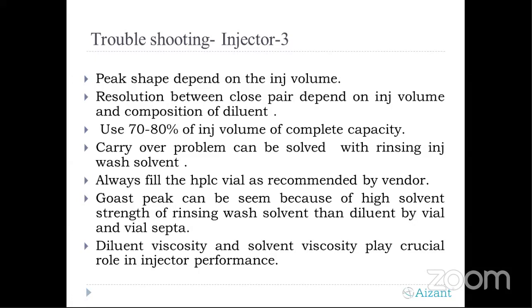Coming to the third slide on the injector, the peak shape of your chromatography is dependent upon injection volume. During development, you can easily cross-check that with variations of 10 microliter, 20 microliter, 50 microliter, and see how the peak shapes come out. It will also depend on the previous point we highlighted, the diluent polarity with respect to the mobile phase. Even if the polarity is different, with 10 microliter you won't face those challenges. But as you enhance your injection volume and the mobile phase remains the same, you will get distortion in the peak shape. So injection volume versus diluent polarity versus mobile phase polarity is very crucial when doing method development.